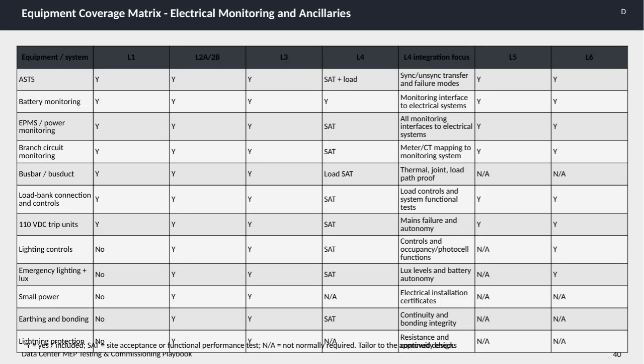This slide presents the equipment coverage matrix for electrical monitoring and ancillaries, which is a key part of our data center MEP testing and commissioning playbook. The matrix details the inclusion and testing requirements for various electrical equipment and systems across different project levels from L1 through L6. Looking at the table, Y indicates that the equipment is included at that level, while SAT refers to site acceptance or functional performance testing. Not applicable means the item is generally not required unless specified by the approved design.